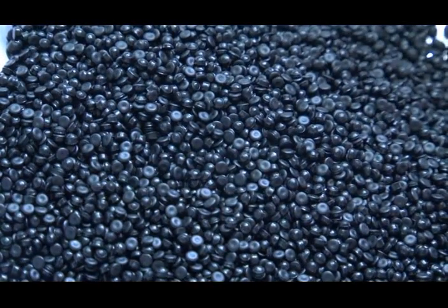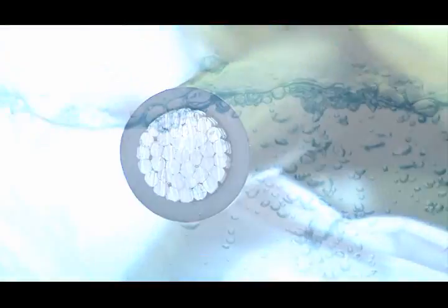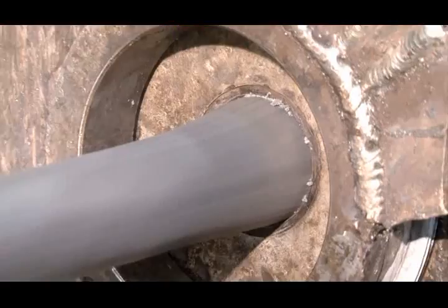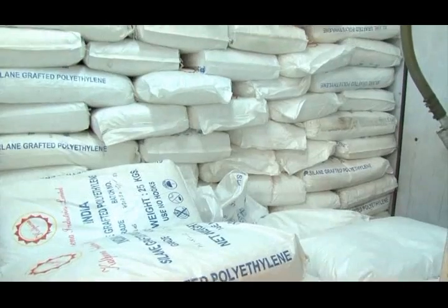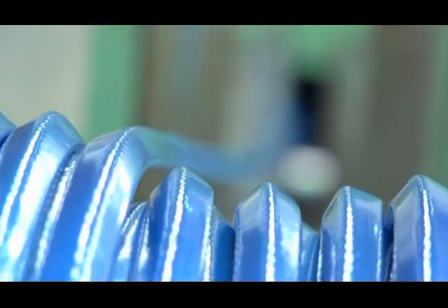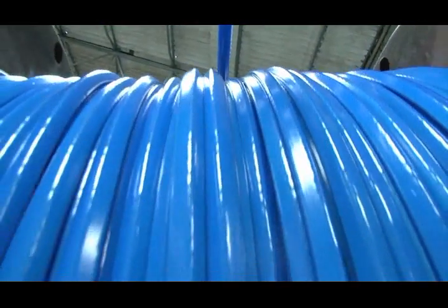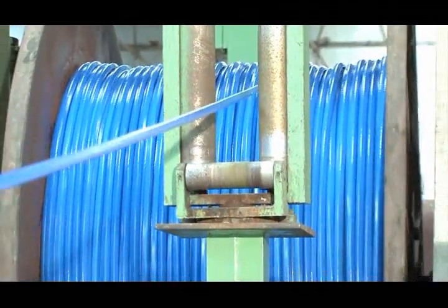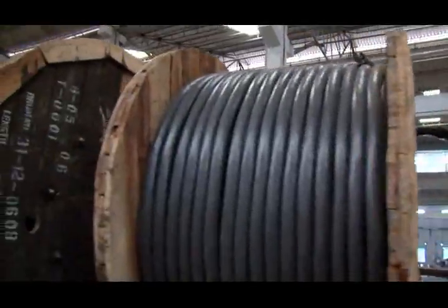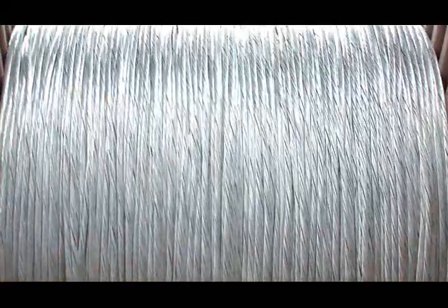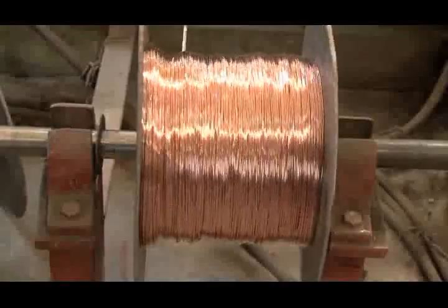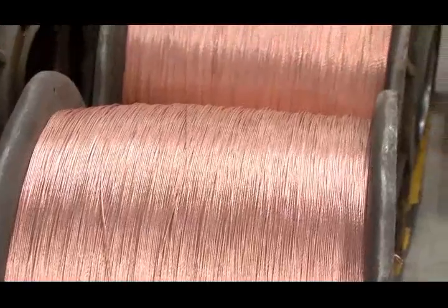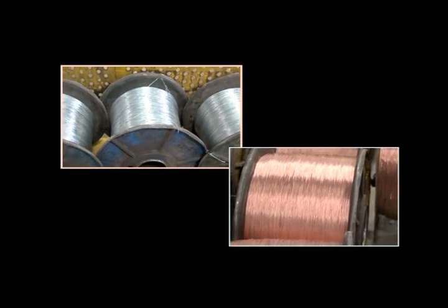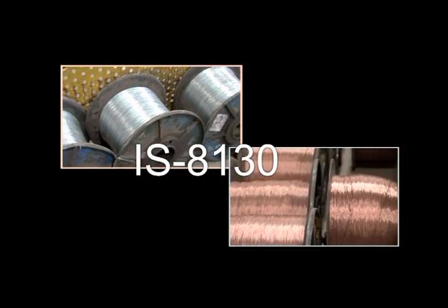PVC as insulating and sheathing material is very strong and resistant to water, oils and chemicals. PVC black compound can resist ultraviolet degradation. Cross-linked polyethylene as insulation material has certain advantages like low dielectric loss, high power rating, resistance to moisture, chemicals and corrosive gases. It also has the capacity to withstand localized temperatures. The power cables are made from pure aluminium and the control cables are made from annealed high conductivity copper. All conductors conform to the IS 8130 standard.